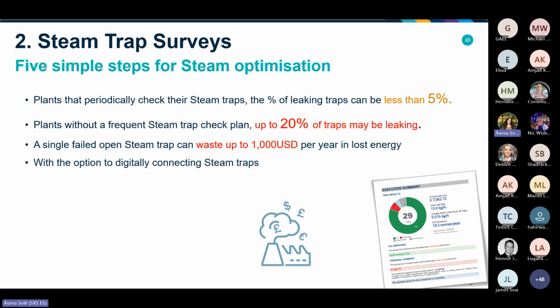The second top solution that we suggest looking at is steam trap surveys. Plants that periodically check their steam traps regularly can have a percentage of leaking traps of less than 5%. But those plants without a frequent steam trap check plan, let's say every 6 months or yearly, can get the steam trap population failing up to 20%. And just a single failed open steam trap, that's obviously an average, can waste up to $1,000 per year. That will be very much dependent on the steam pressure at that line and on the steam generation, but that's just a rough estimate for you to see that the potential impact we can reduce is significant.